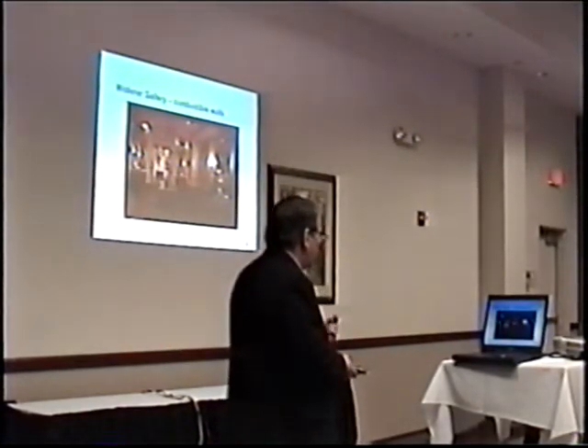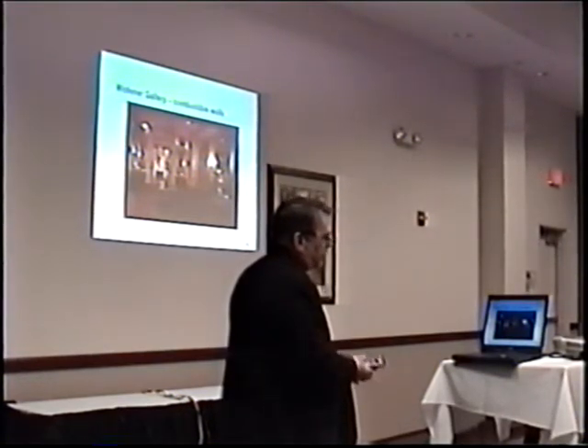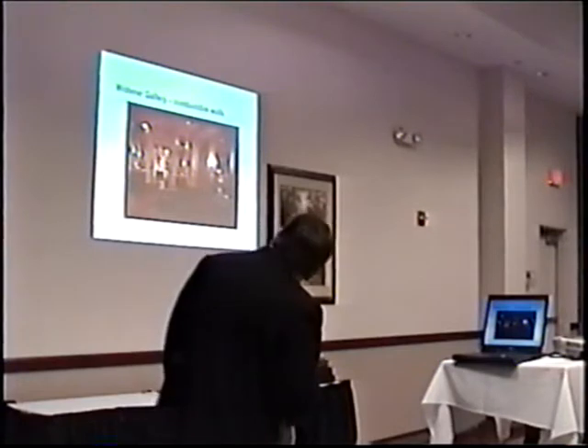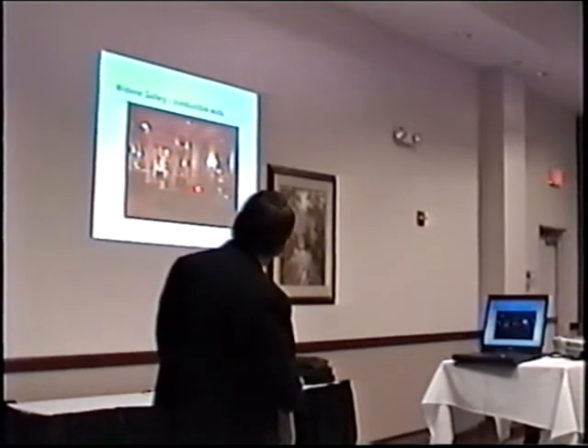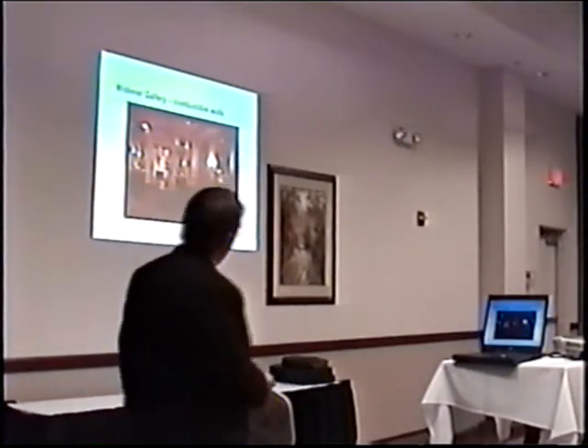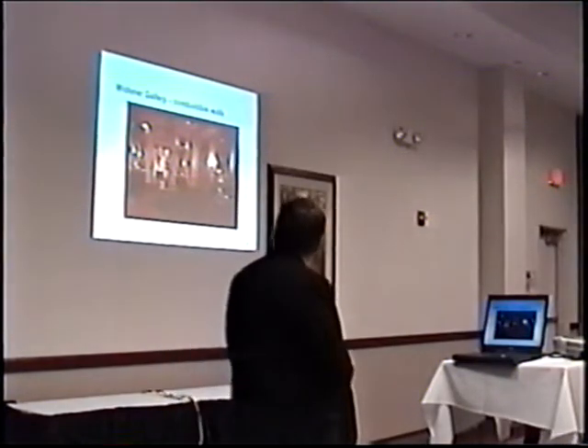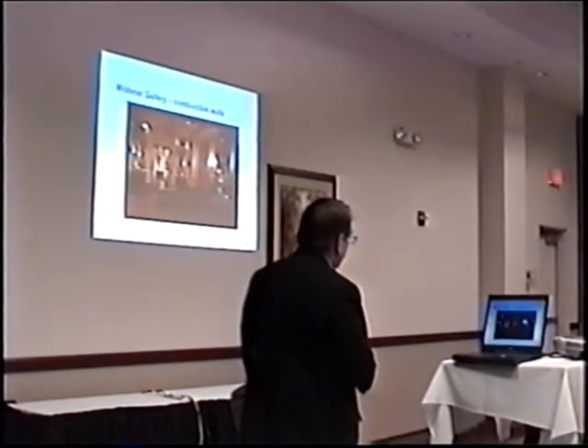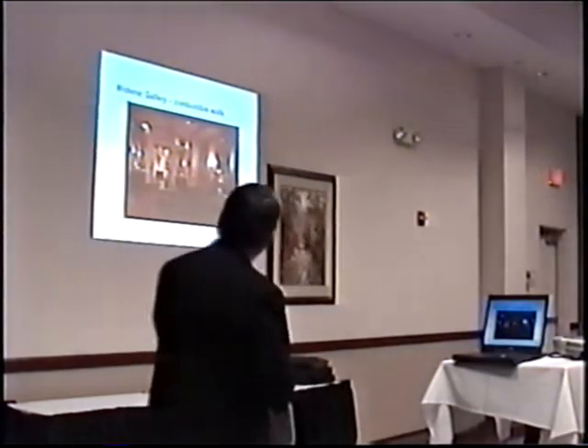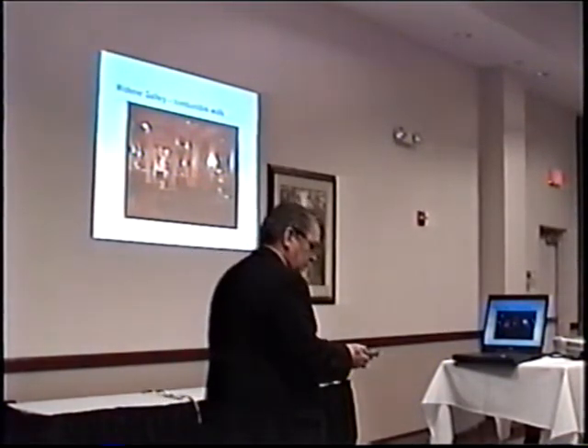So let's get into the first phase of this, which was to design a water mist system and put in the basic infrastructure for a system to protect two specific small galleries. Difficult to see there, but this is called the Widener Gallery. These are 15th century panels from an Italian villa, and all combustible. They're mounted on steel studs with a cavity behind there with a concrete wall around it. And so it's all basically combustible wall paneling.